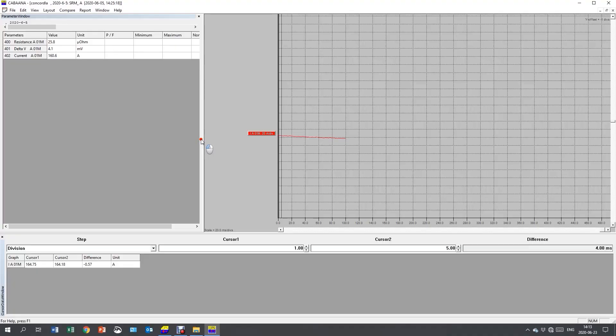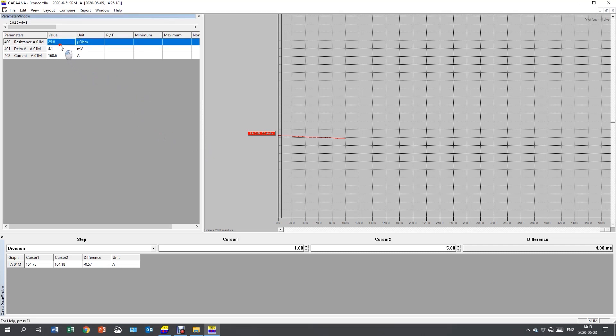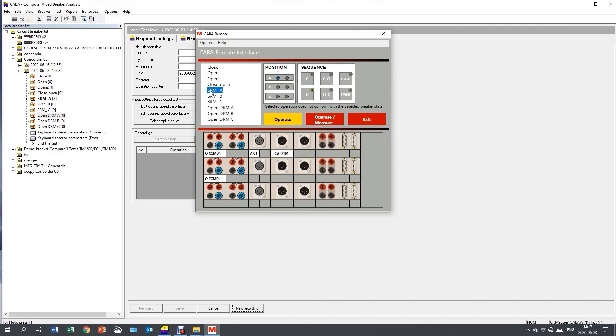The static resistance value occurs on the screen. I can read out the value 25.8 micro-ohms. I can close the window and continue to do two to three more measurements to see that the result is constant.